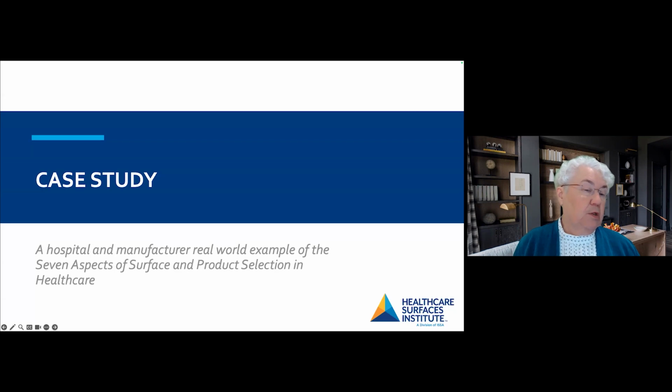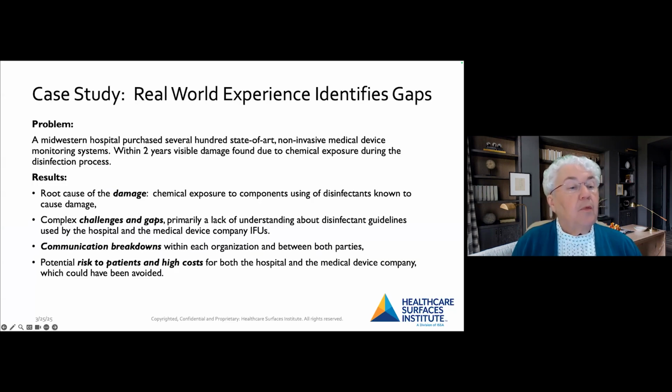in healthcare. Next slide. So the problem was a Midwestern hospital purchased several state-of-the-art medical device monitoring systems, but within 2 years, they saw visible damage found due to chemical exposure during the disinfection process.